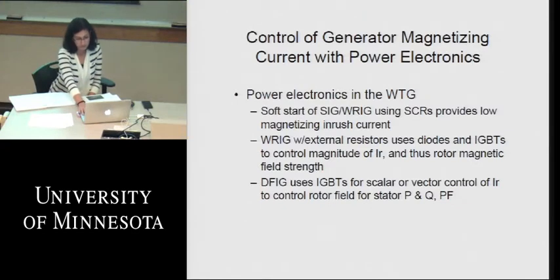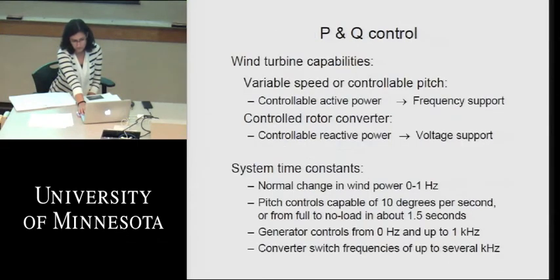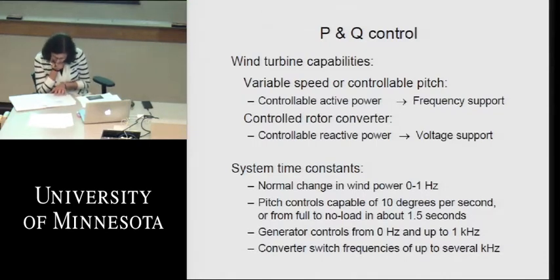So with active and reactive power control, fundamentally, if we control the speed of the operation by pitching, then we control active power. If we control active power, we can actually affect frequency regulation and frequency support. By controlling the rotor converter and controlling reactive power from the generator itself, we can actually affect voltage regulation and voltage support.